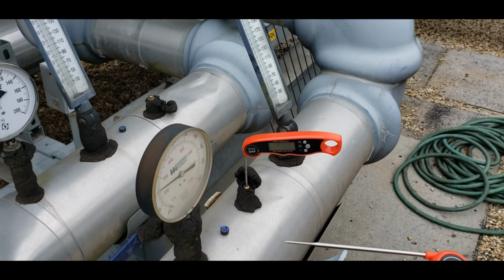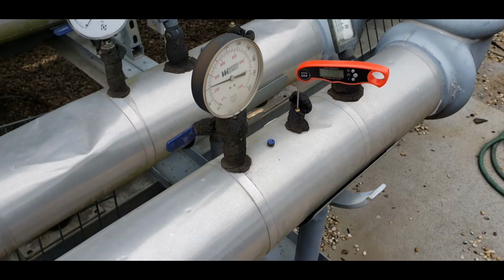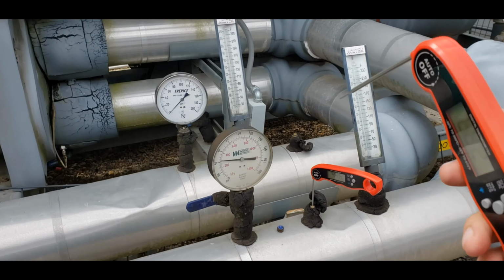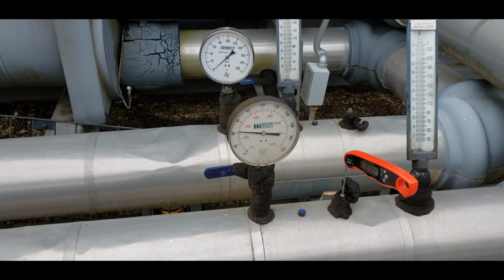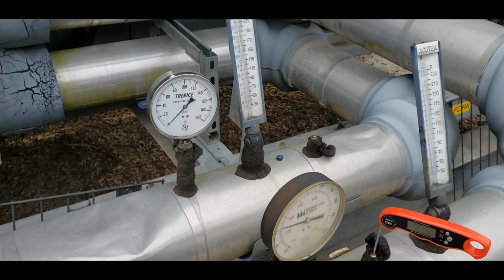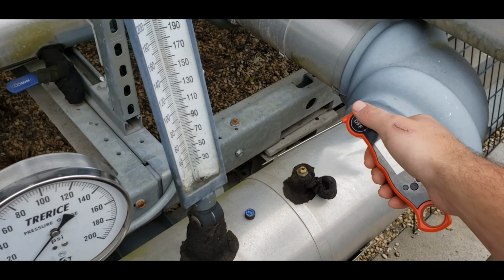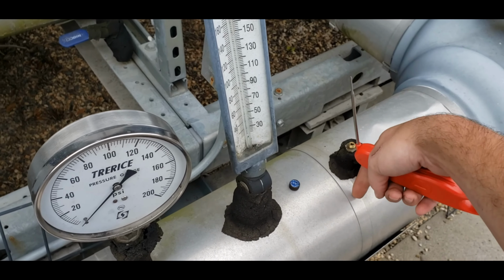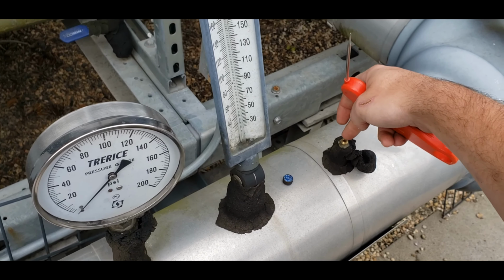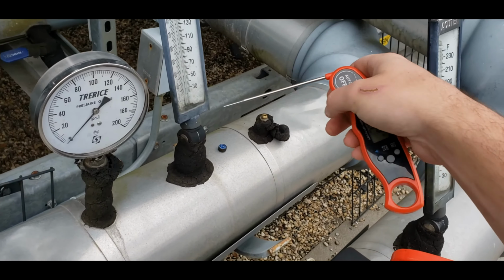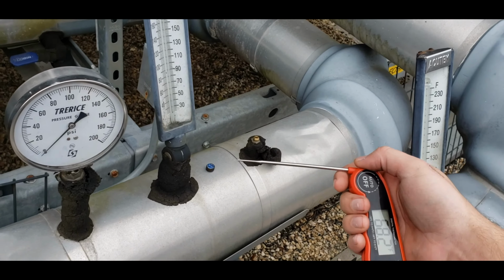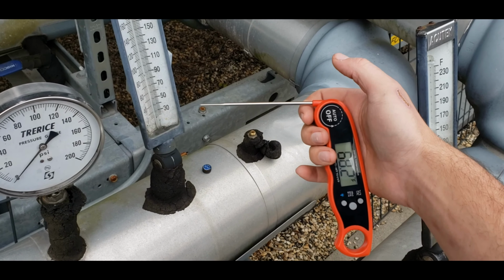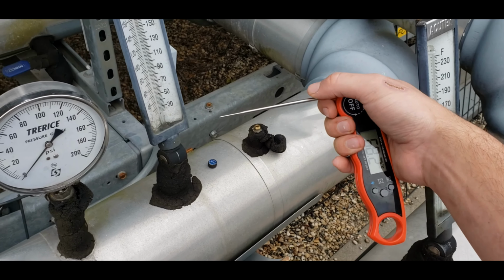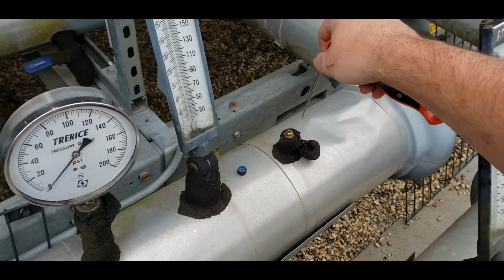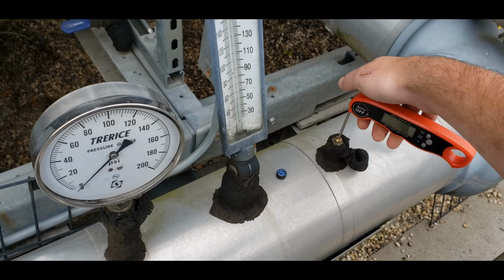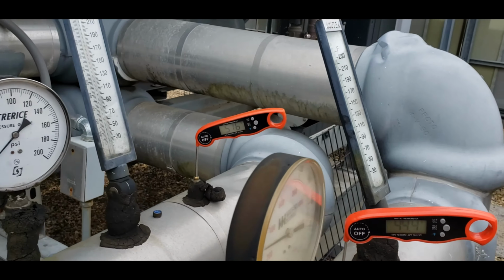So part of what I'm doing right now is I'm checking calibration on all the sensors. Now if these thermometers and these pressure gauges aren't reading correctly, I'm going to recommend replacement on those. And then these have Pete's plugs on them. What this is, is just a plug that sticks down into the water, but it's got a rubber grommet in there that you can shove a needle through and either get a pressure reading, temperature reading, whatever. What I found is these little grill thermometers I found on Amazon, but the needle tip on them is small enough they'll actually fit down inside there just perfect, where we can actually get a reading on them.